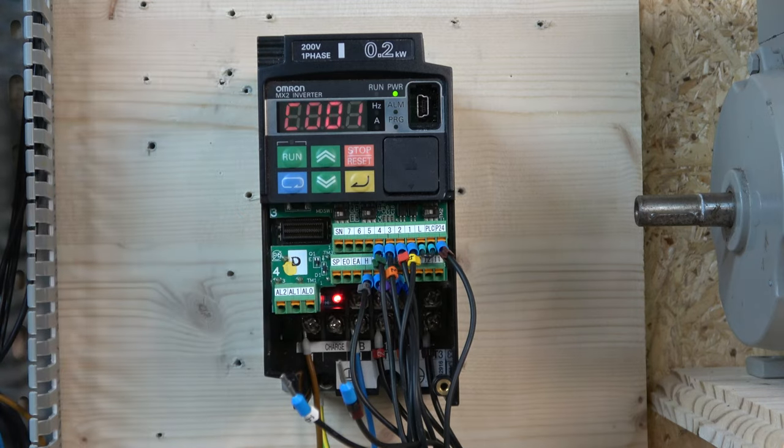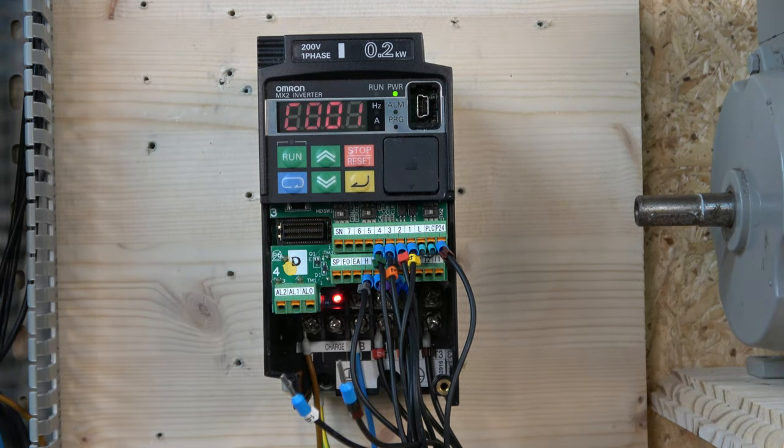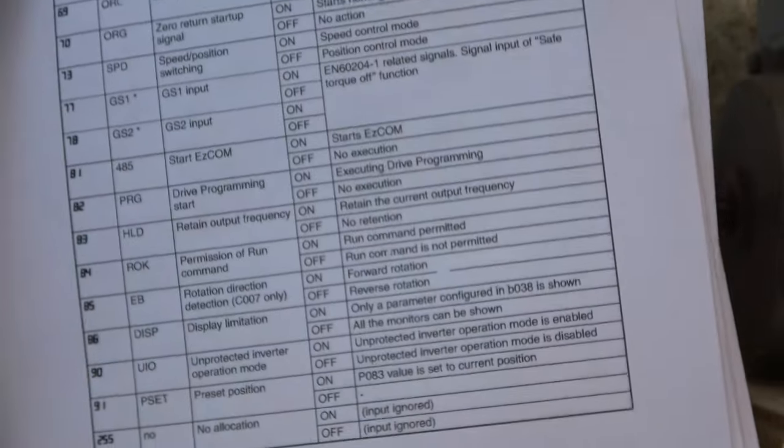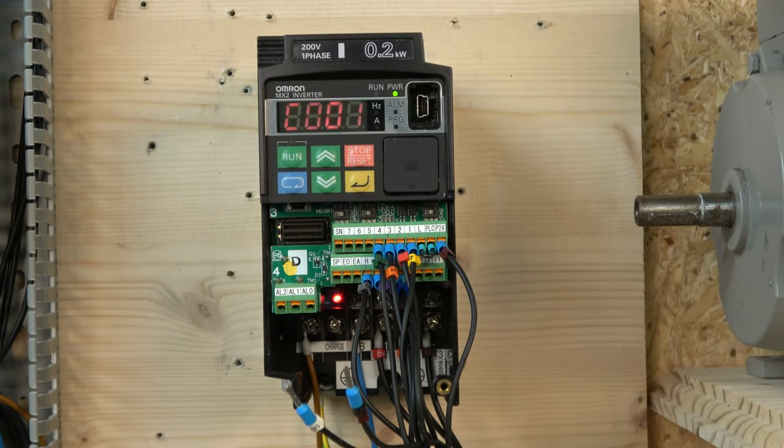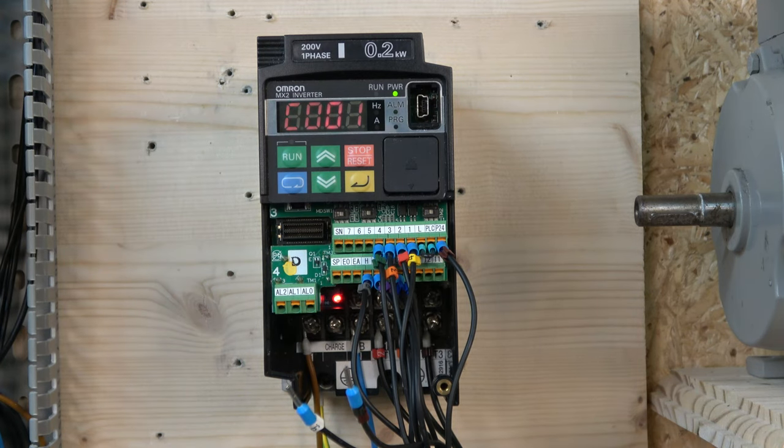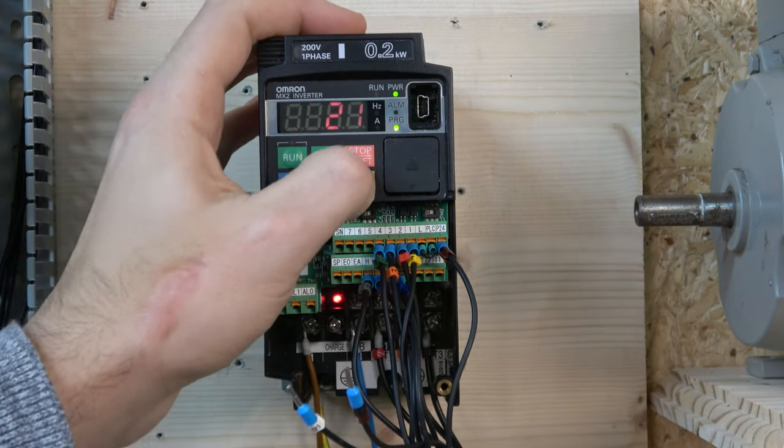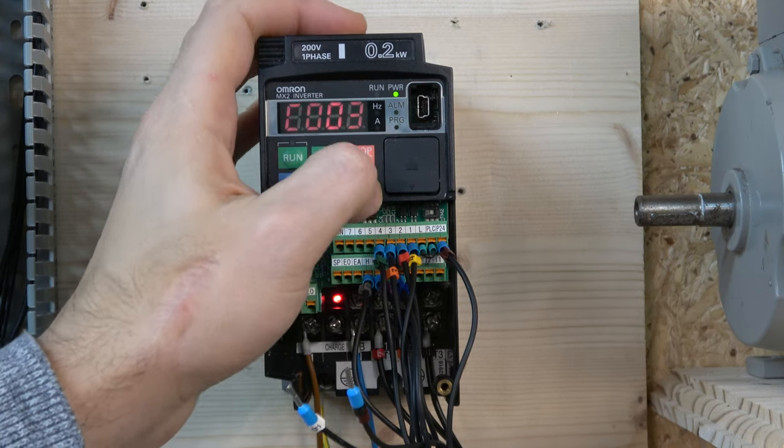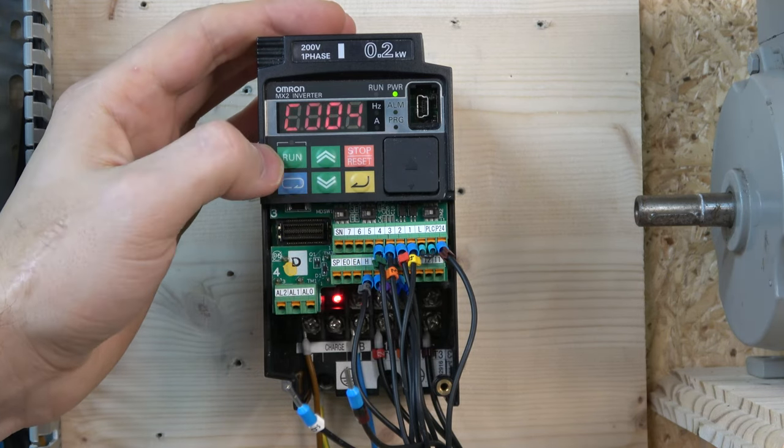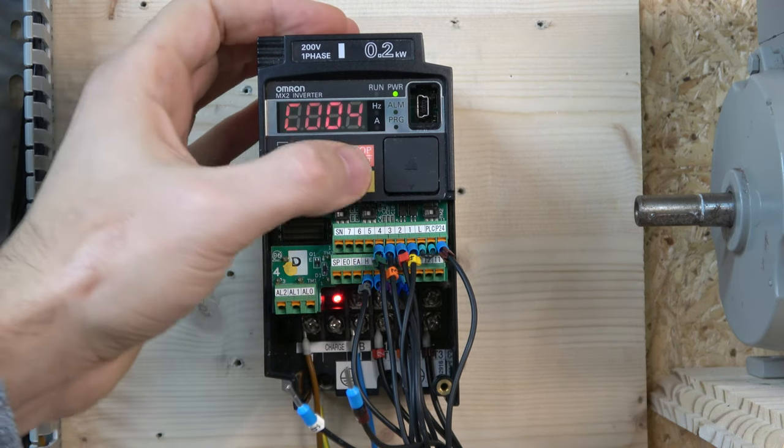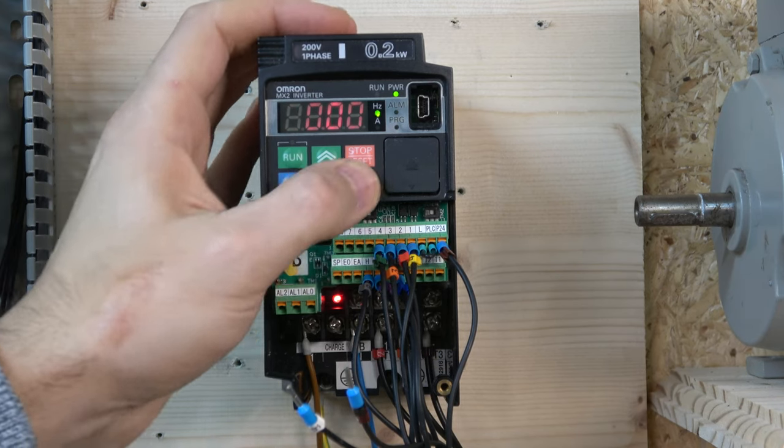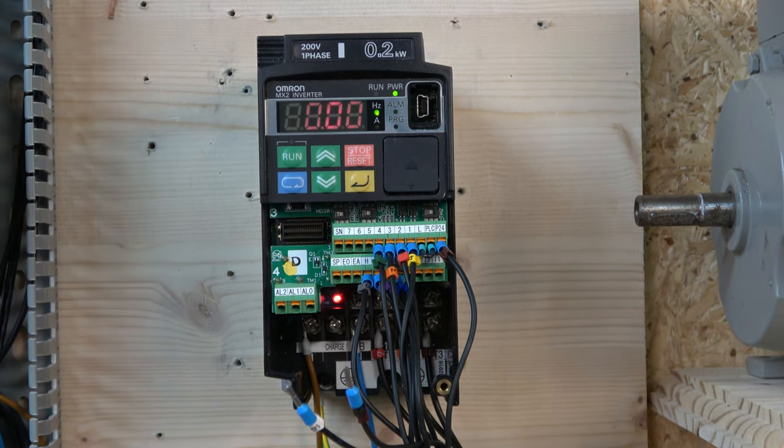To do that you need to go to C, and C1, 2, 3, 4, 5, 6, and 7 is pretty much corresponding to 1, 2, 3, 4, 5, 6, 7 in here. And each one of them you can add any of these digits. And guys, there is ton. I mean there is approximately four or five pages of options these digital inputs can do. Omron did not get shy about putting a ton of options that you can do with these inputs. So yeah, do check them out. As you can see in here I've got 20 in there, 21 in there, 12 still there for the external trip, and the fourth I have 22. So pretty much once I entered all them in, the whole system is pretty much ready to go. That's pretty much all the things you need to do. Let me put the cover on and I'll show you how that works.